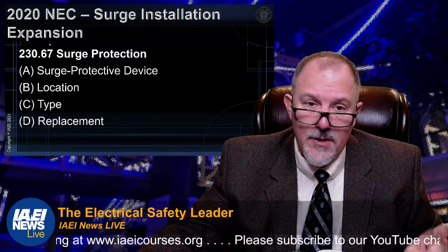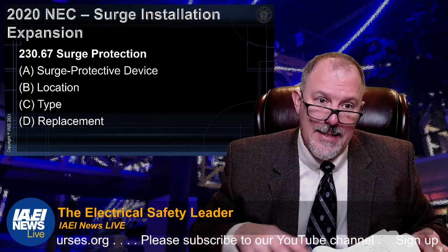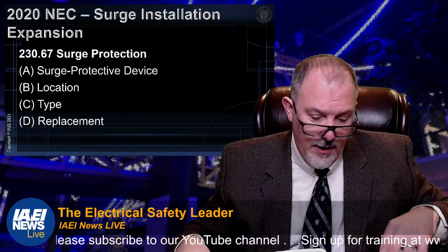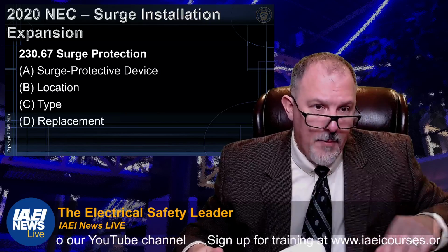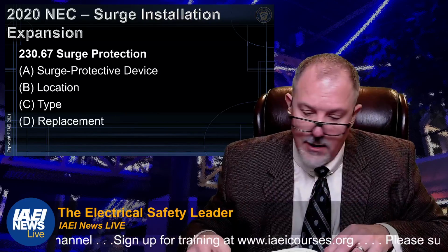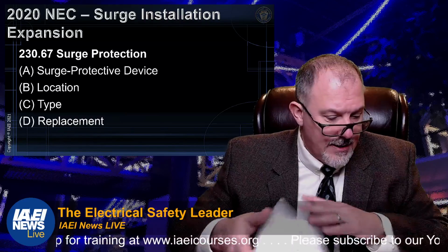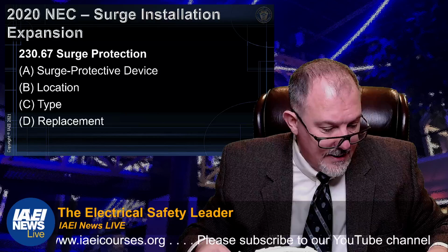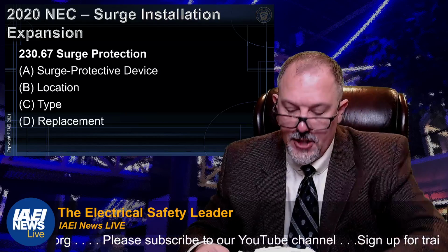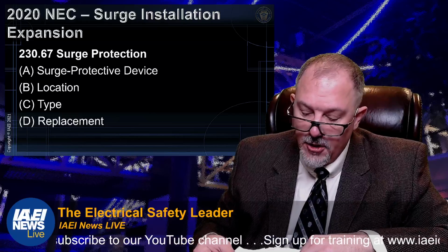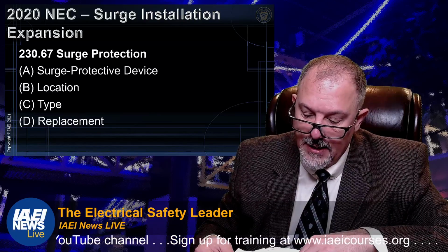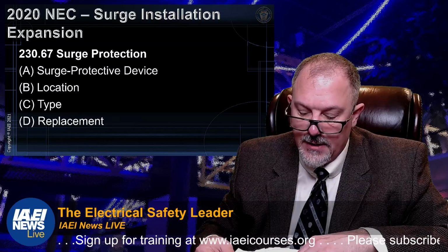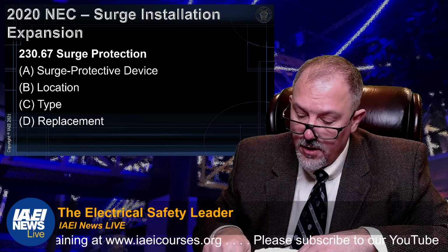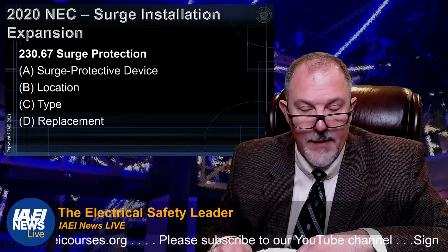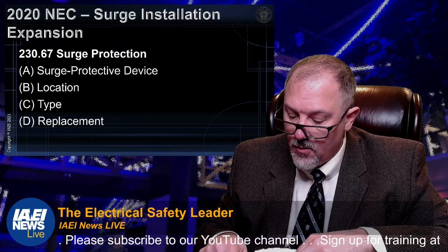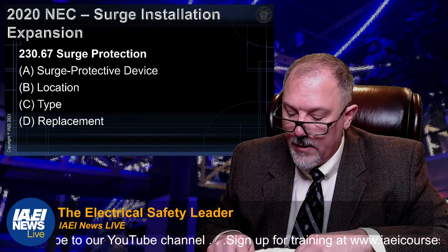Now in 230.67, so this is the 2020 version of the NEC, and they did expand surge requirements in Article 230. And my book is just falling apart. Article 230. Let's take a look. 230.67. 230.67. The whole section is new. Surge protective device. All services supplying dwelling units shall be provided with a surge protective device. This is in 230.67A. That's A. All services supplying dwelling units shall be provided with a surge protective device. The location. The SPD shall be an integral part of the service equipment or shall be located immediately adjacent thereto.